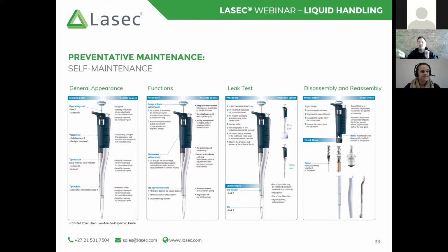If I were to replace the tip holder with another tip holder, it is possible that it might not have the same defects, or it might have greater defects, for example. So now we've no longer calibrated it for that assembly.